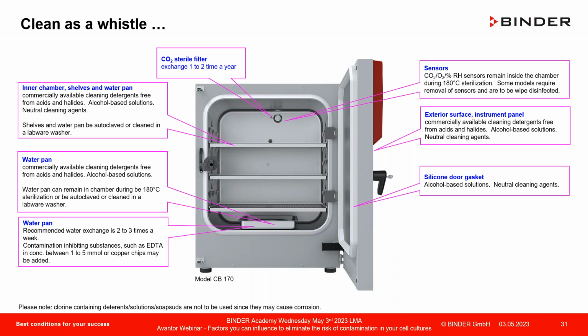The sensors themselves, depending upon the model, temperature sensors are heat resistant, CO2 sensors are heat resistant, oxygen sensors and humidity sensors are also heat resistant, and can be hot air sterilized. Other models require you to remove, for example, the CO2 sensor and conduct a wipe disinfection with very common disinfectants you have in the laboratory.